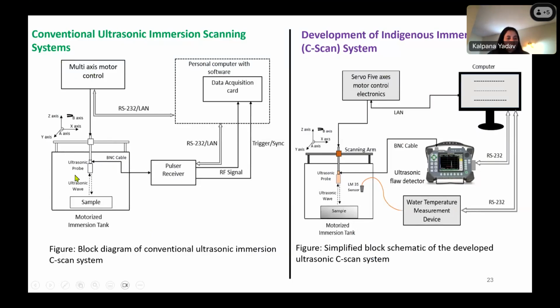So this is the ultrasonic immersion tank, where you put your ultrasonic probe, and this probe can have angular, translational, and linear motion, and it is connected to the pulser receiver. The pulser receiver is connected to a data acquisition card that acquires your data, and that is controlled by a personal computer with software to control the card, connected via RS-232 or LAN communication. And this multi-axis motor is basically a servo motor based system, so it can control the motion of the probe, and it can be rotated or moved the way you want, for the amount of scanning you want for the testing.